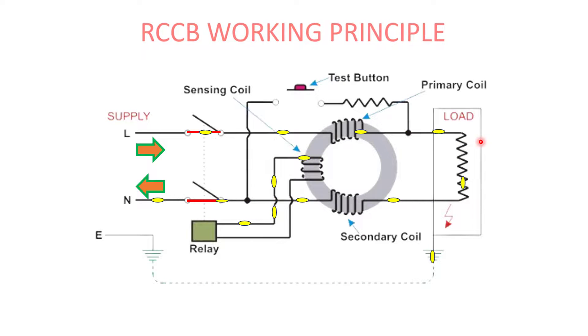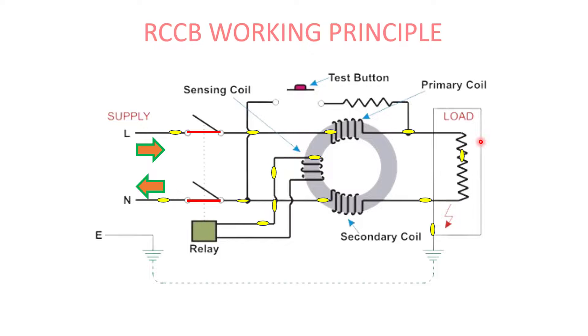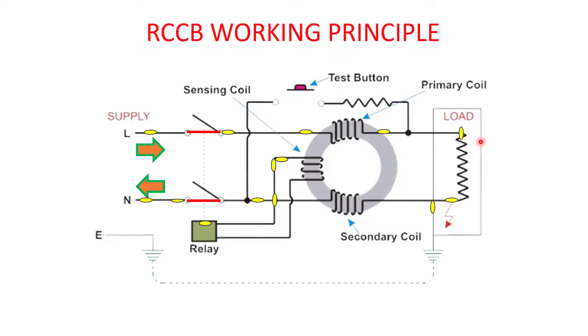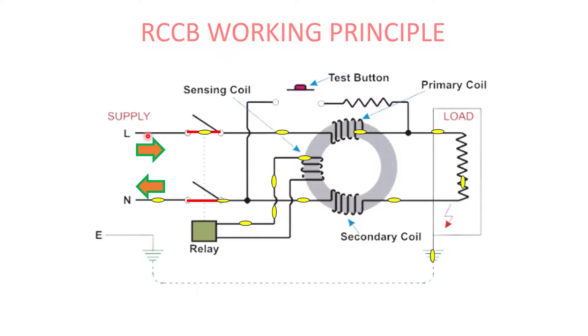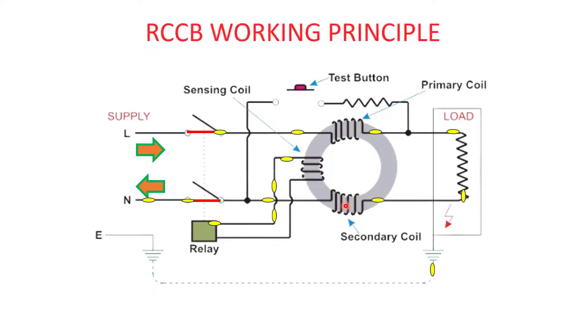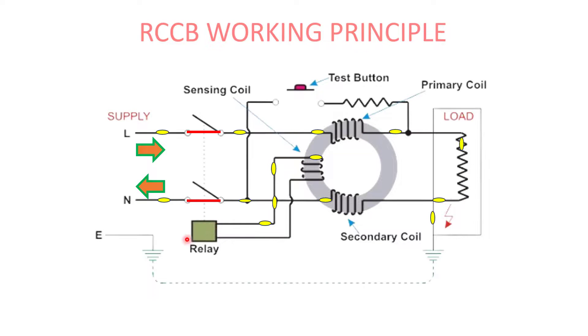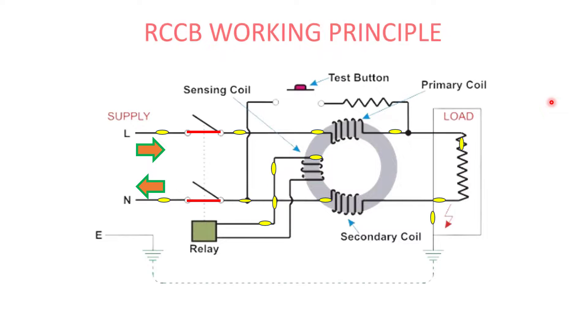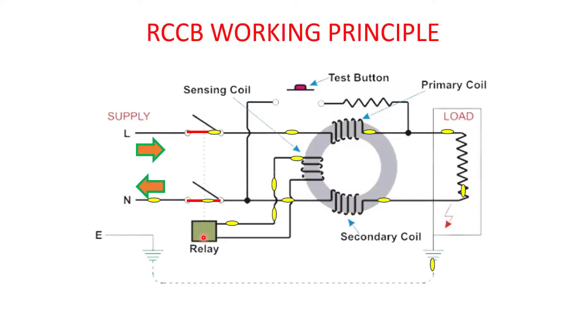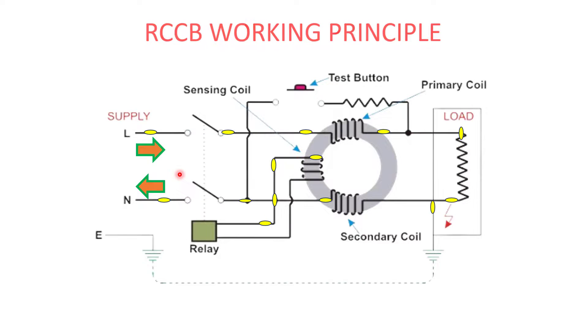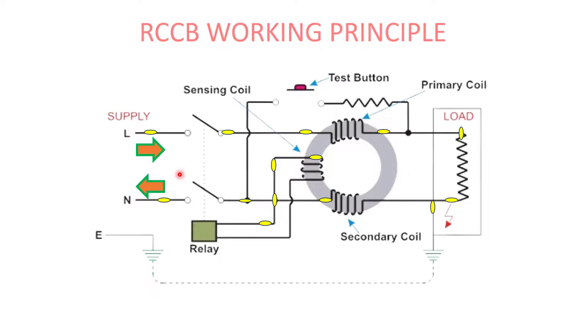If a ground fault occurs or a human body comes into contact with the circuit, current flows through the body or object to the ground. This causes an imbalance in the magnetic fields — the primary coil's magnetic field is higher while the secondary coil has a leakage, so the opposing effect is lost. An induced EMF is produced in the sensing coil, which triggers the relay attached to it. The relay is an electromechanical switch — when current passes through it, it triggers the mechanism and opens the circuit. Once the ground fault occurs, the relay energizes and causes the RCCB to trip, breaking the circuit.